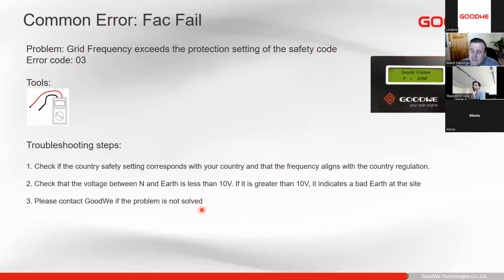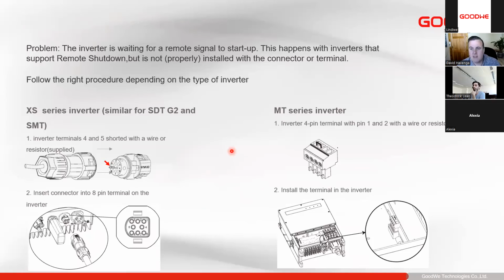Next, Fac Fail, it's the frequency of the utility. So you can see that the frequency is within your country regulations as well. Same for the voltage between neutral and earth, just make sure that it is correctly connected. And lastly, if it still persists, please contact support.